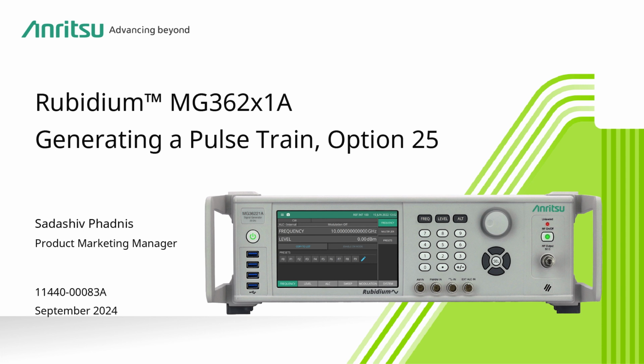In this video, I'll be explaining Rubidium's capability to generate long pulse patterns using pulse train option 0025. Rubidium's pulse modulation option enables users to generate up to 4 pulses in a single pulse period, each with different delay and pulse width. The pulse train option extends this capability. With pulse train option, users can generate up to 2048 pulse bursts, each with different delay and width.